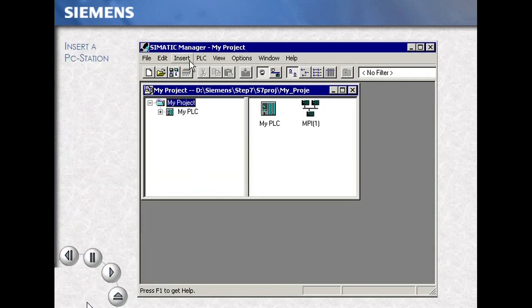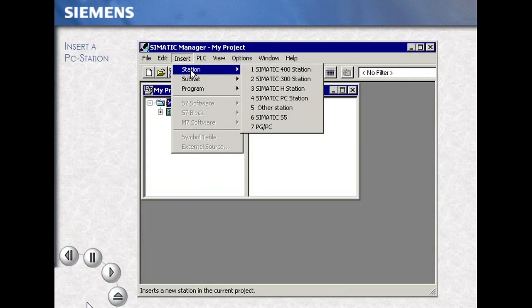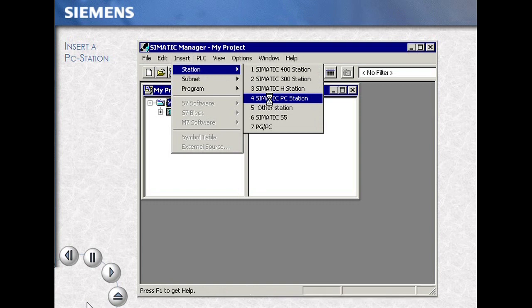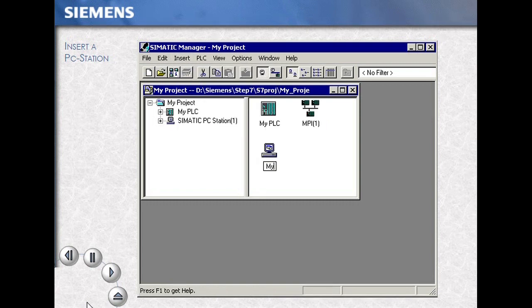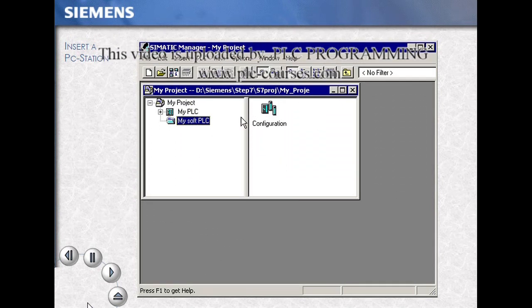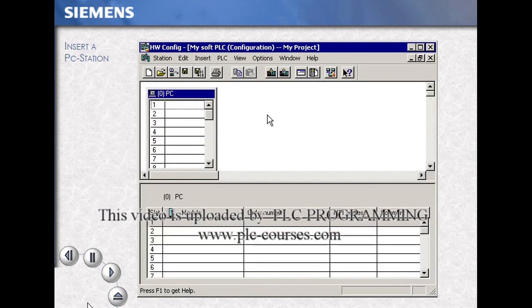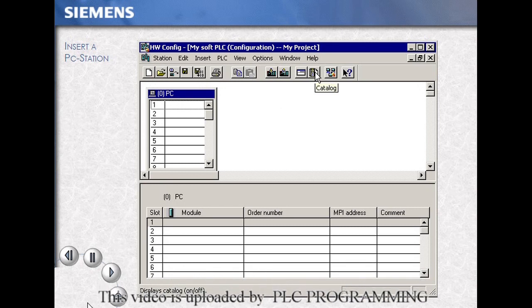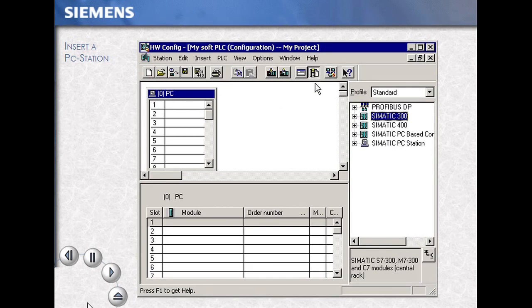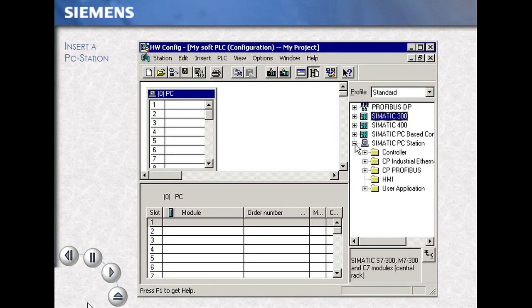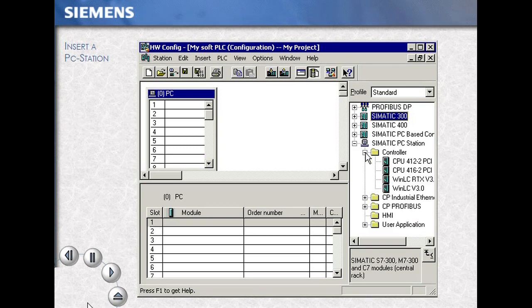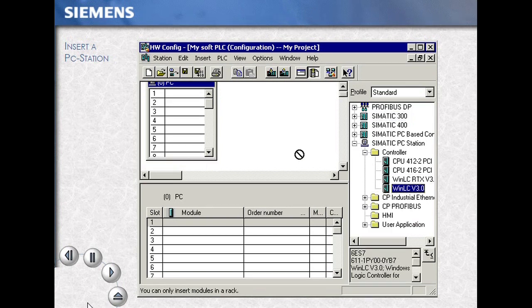Using the menu items Insert, Station, select SIMATIC PC Station. Name your station — this example, MySoft PLC. Open your station and select the Configuration icon. This opens the hardware configuration tool. Open your product catalog. Expand the PC Station directory, Controller. In this case, our selection is WinLC V3.0.